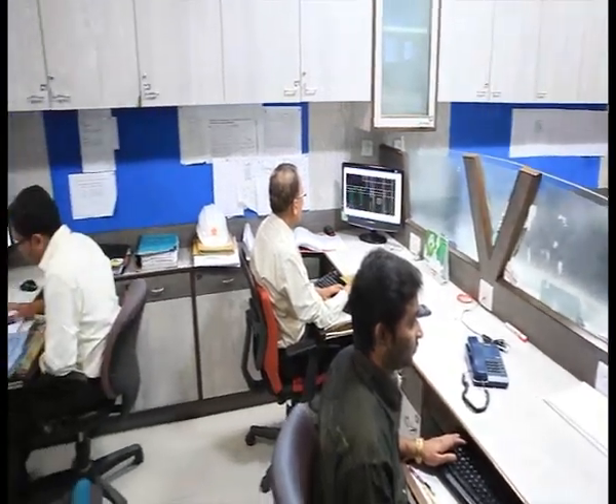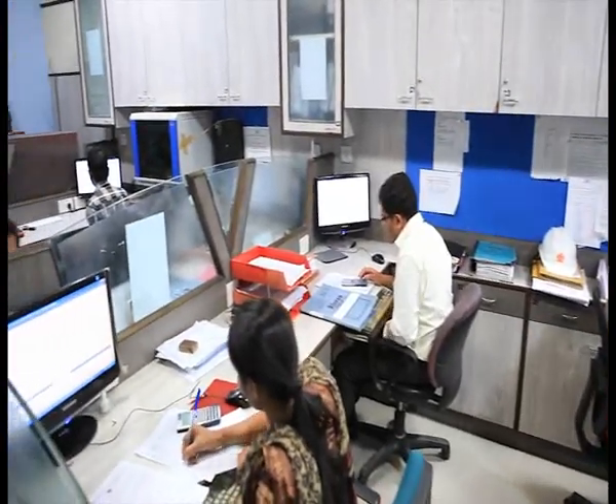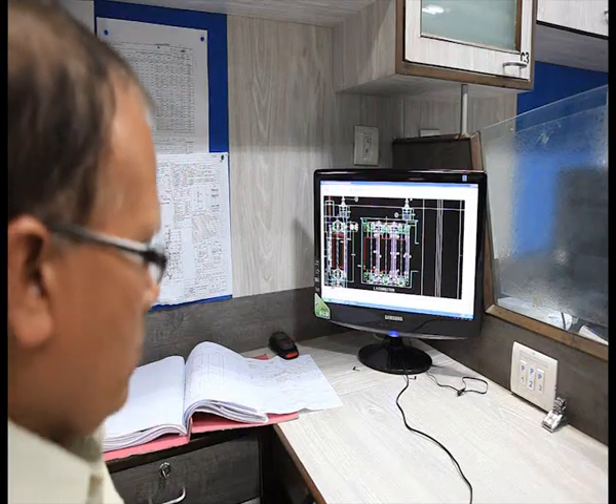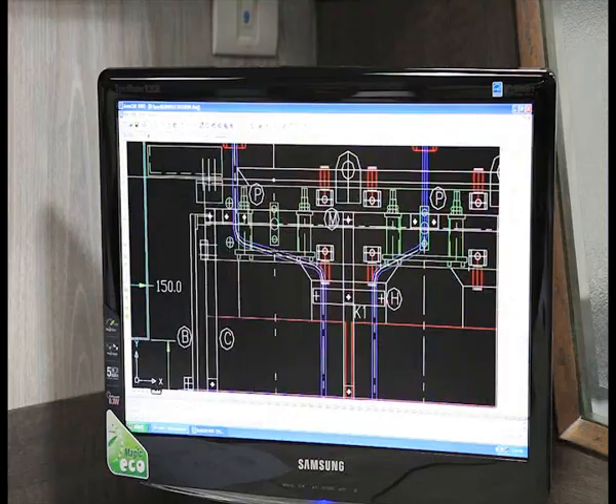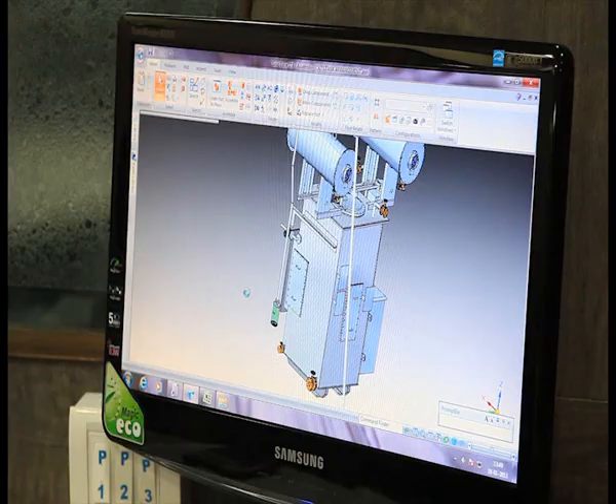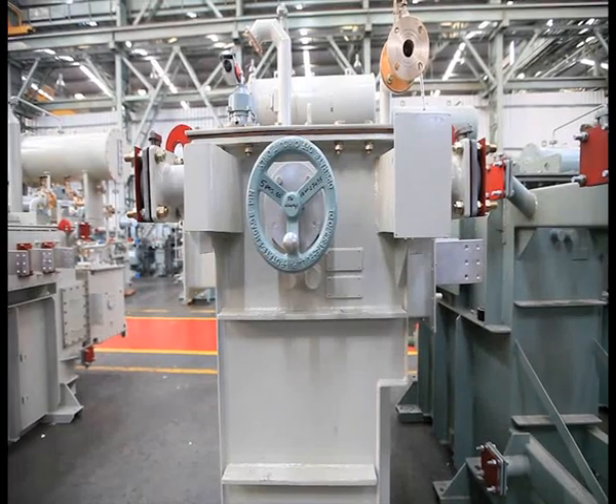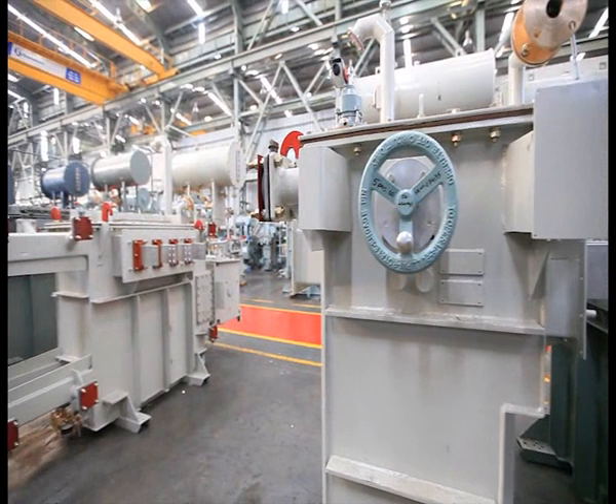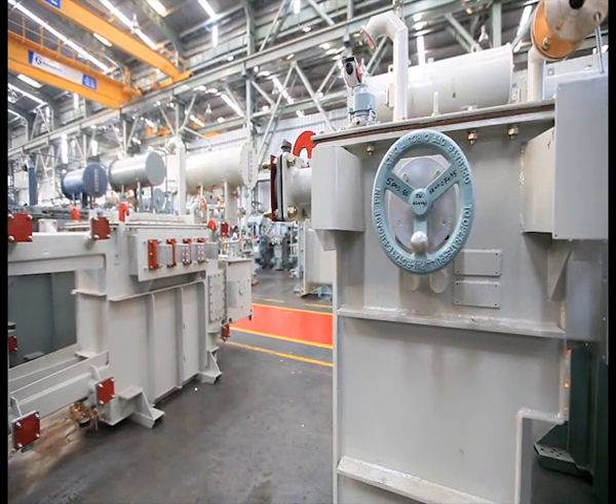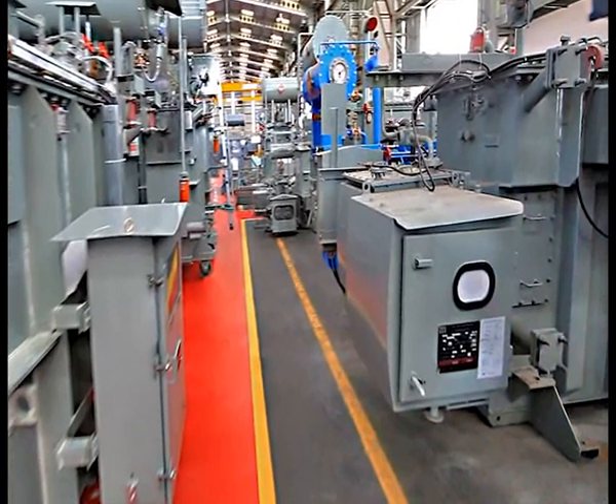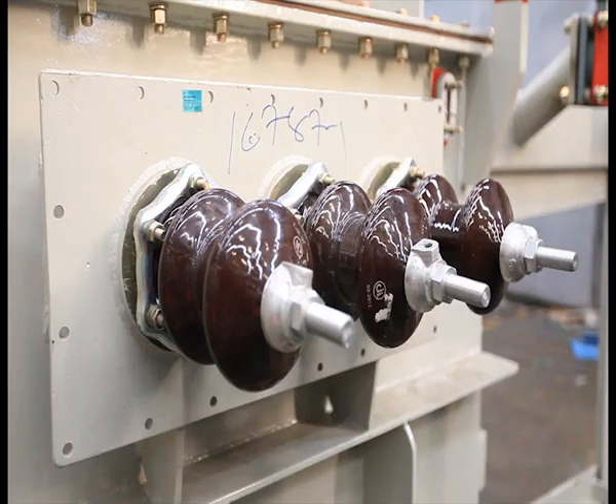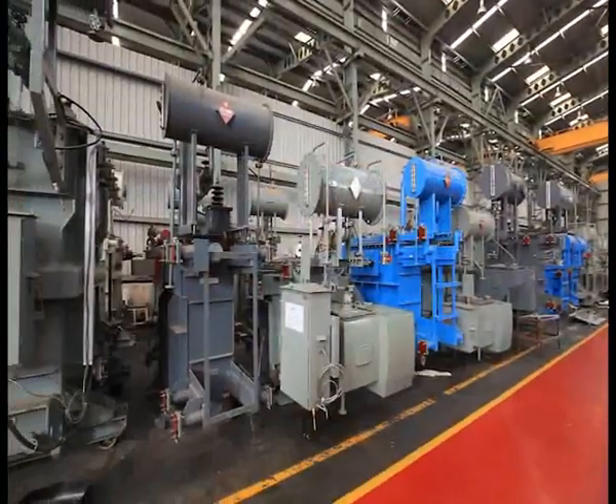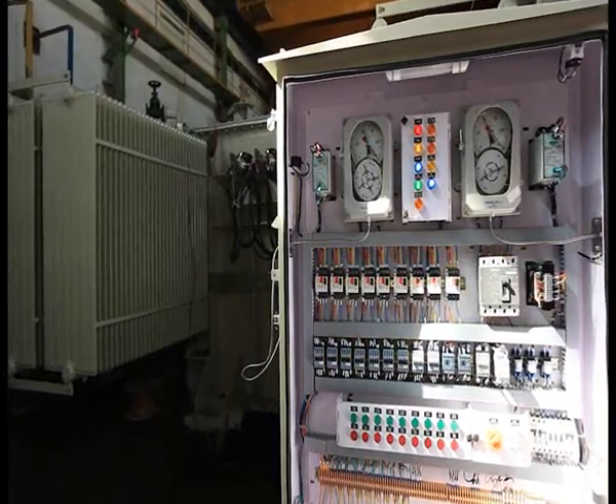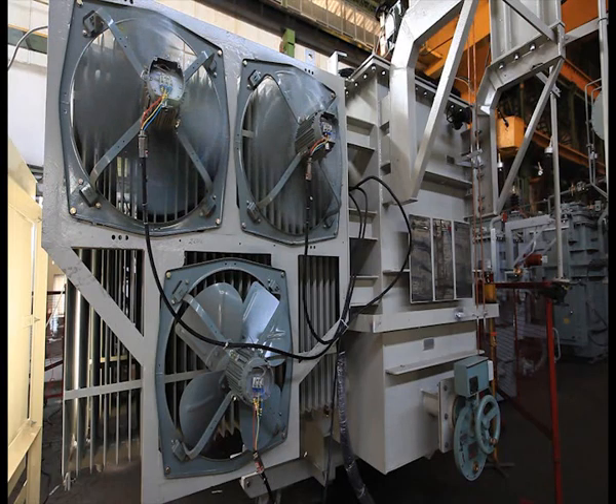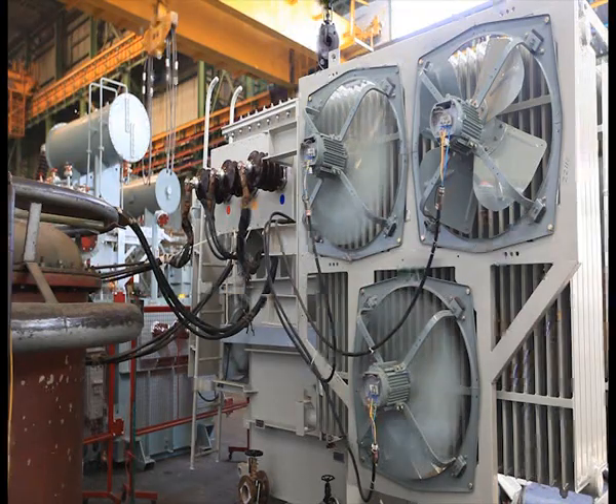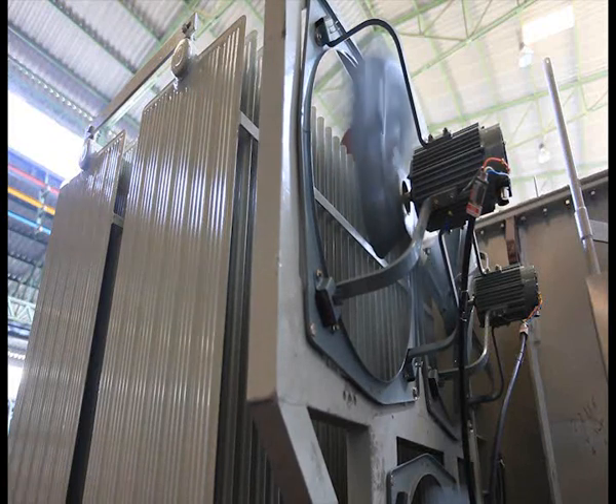The SAS division has comprehensive design data of the transformers undertaken for repairs. In some cases, we advise on modifications and alterations in design to increase the life and quality output of the transformers. Moreover, transformer conversion or modification needs of customers, such as off-circuit switch to on-load tap changer for voltage variation, change in vector group and voltage ratio, are also undertaken at our end. We also provide adequate capacity enhancement solutions to customers for their transformers by providing additional cooling wherever feasible.